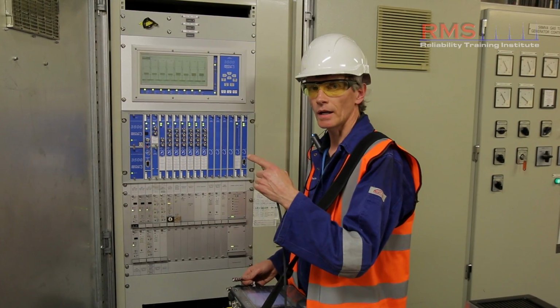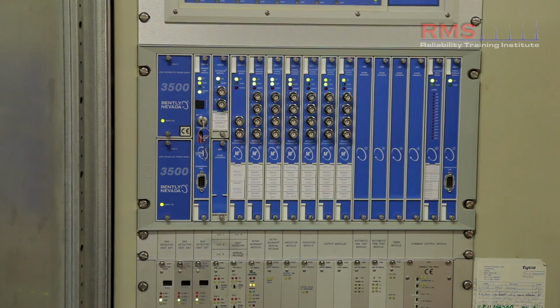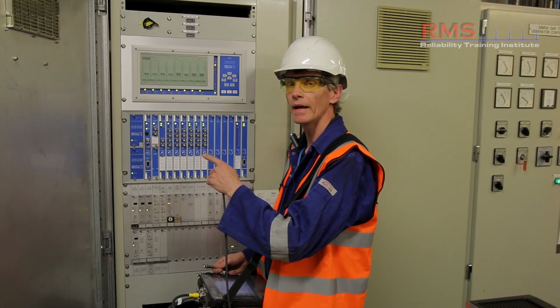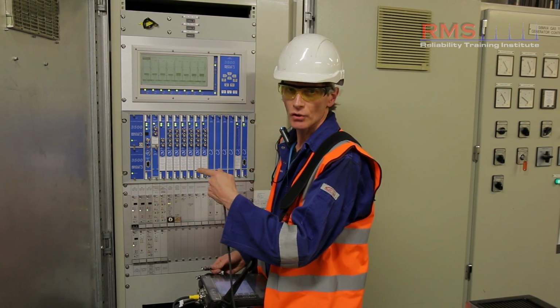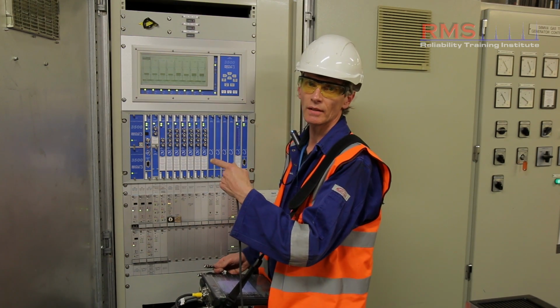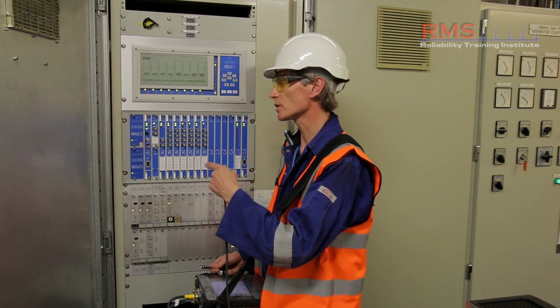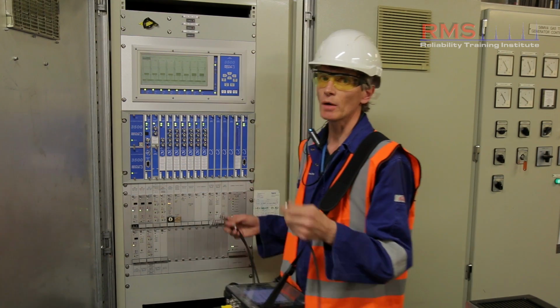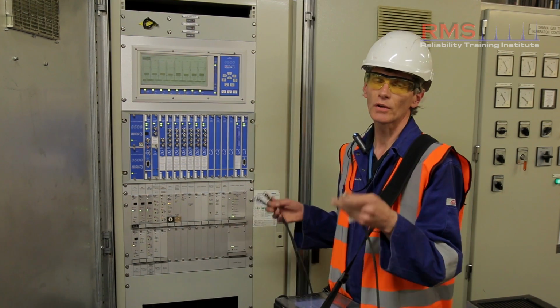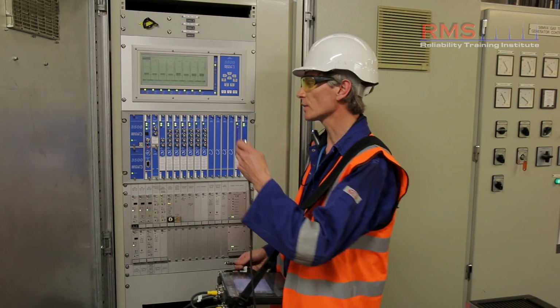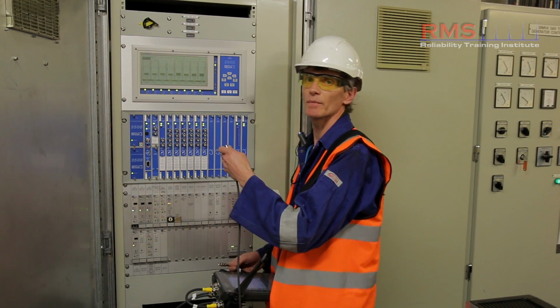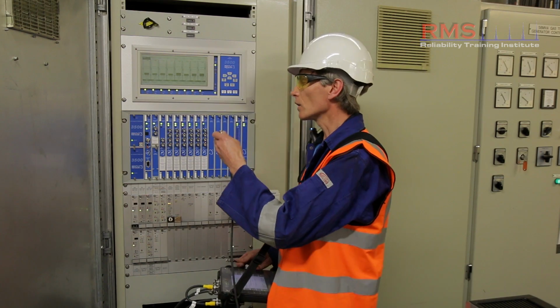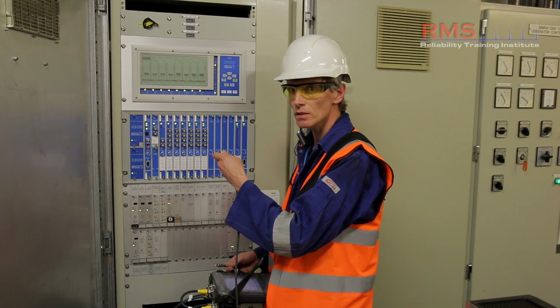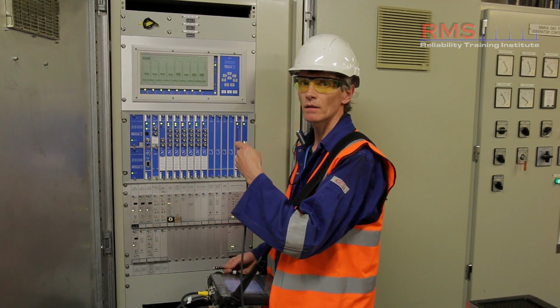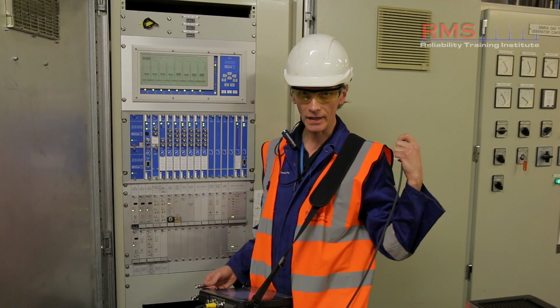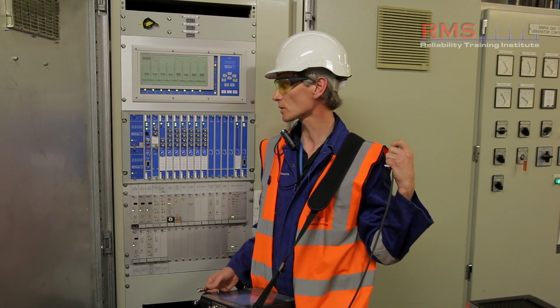Okay, so here we are at the gas turbine protection system. It's important to understand that a protection system is there in the event of a catastrophic situation happening, some sudden change in machine dynamics that is going to cause damage to the machine, that would shut the machine down. The purpose of what we're going to do now is actually more focused on prediction. So we're going to plug into the XY probes and any casing measurements that may be applicable as well, and look at the dynamic movement of the shaft in free space and predictively trend the heartbeat of the gas turbine that we spoke about a few seconds ago outside.